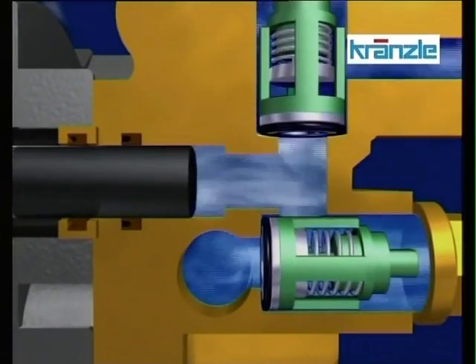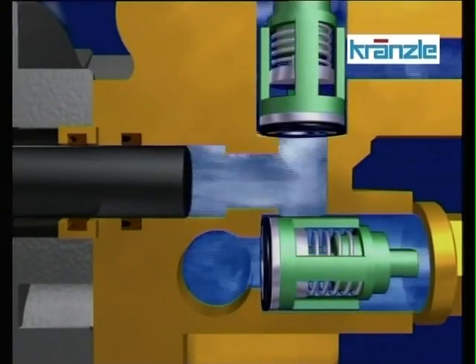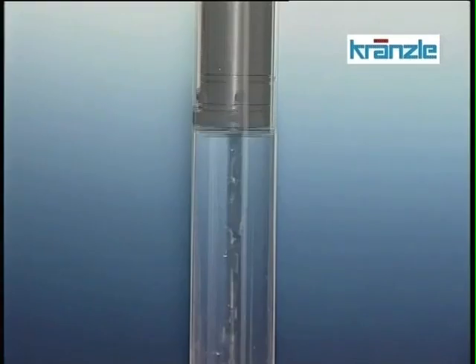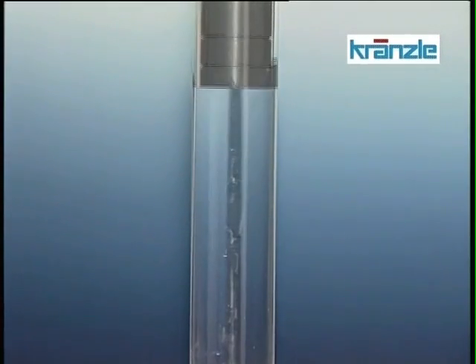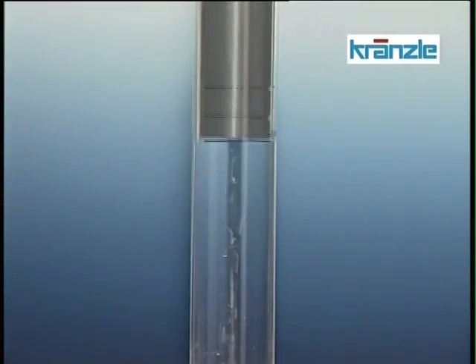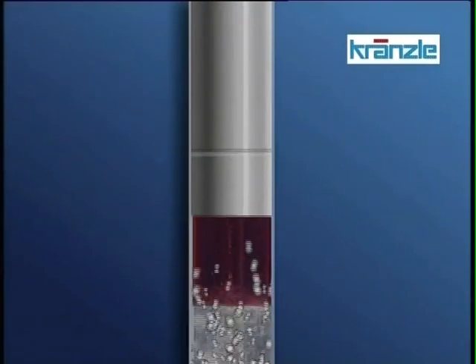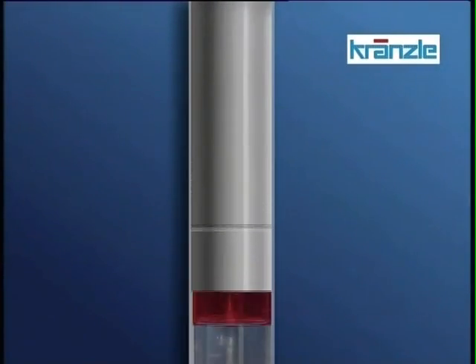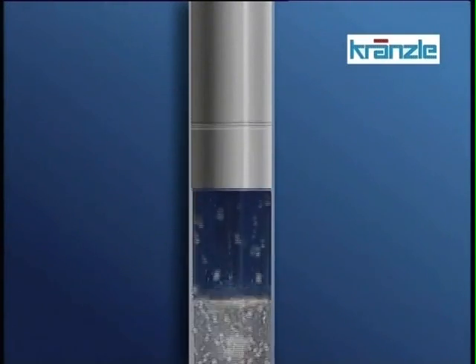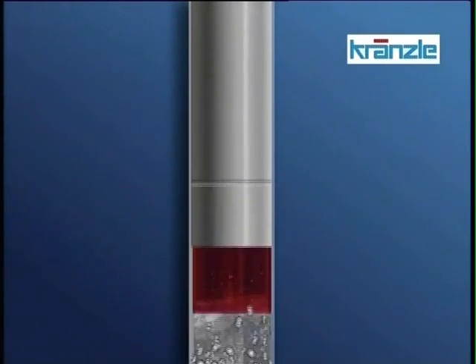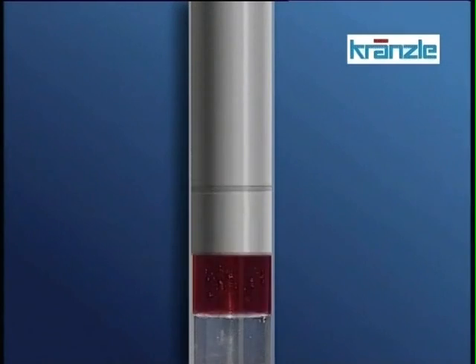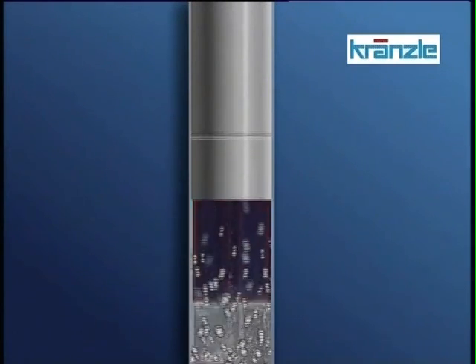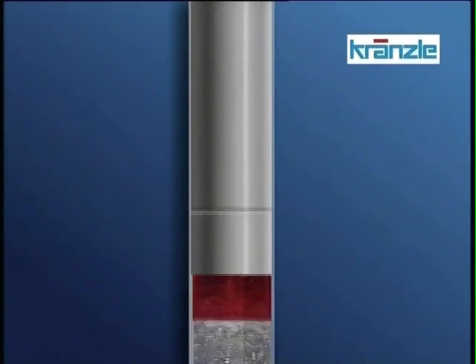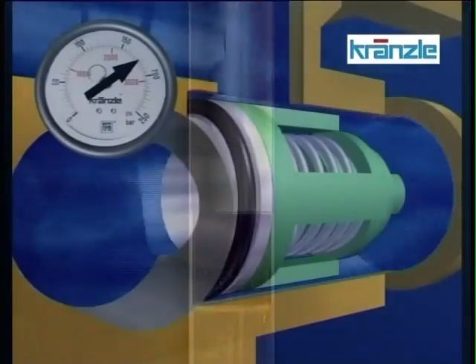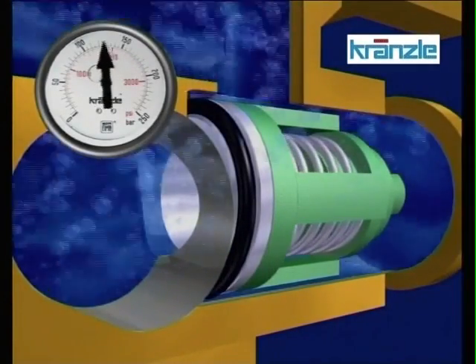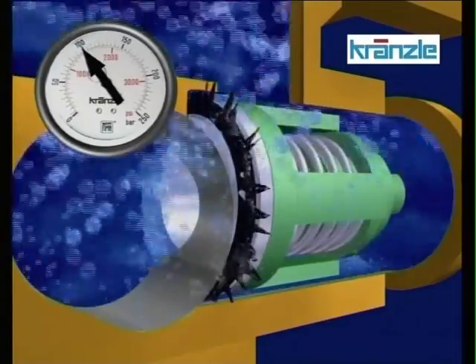This is to illustrate that the high-pressure pump receives enough water, that the chamber in front of the plunger is filled with water, and that the high-pressure cleaner functions properly. And here, another more simplified view. In the event of insufficient water, a vacuum or negative pressure is produced. This causes the release of air and gases which are normally bound in the water, as well as cavitation. And by the way, the higher the temperature, the faster this process takes place.